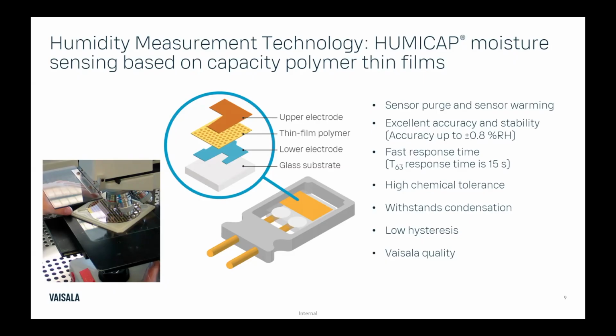So now our new technology works like this. You have an upper electrode, a thin film polymer, and a lower electrode, all stacked on top of a glass substrate. The water vapor penetrates through the upper electrode and is absorbed by the polymer. How much water is absorbed is dependent on the ambient relative humidity. When that water gets into the polymer, that changes the dielectric properties of the sensor. And then we can measure the capacitance between the two electrodes and calculate the relative humidity, as well as several different moisture parameters.